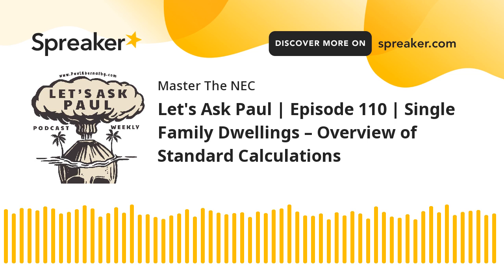Now you're saying, but didn't it say general illumination? Why are we adding the receptacles? Because 220.14(J) told us that all of this load is to be incorporated in one usable value. And that's what we're doing. So we're allowed to apply all of these, in case that ever gets confusing for you. Now, the second thing you're probably thinking is, well, yeah, but what about the small appliance and the laundry? Well, if you go look at 220.52(A) and (B), you'll notice in the very last sentence, it tells you that these can be subject to the demands of Table 220.42. So that's why we can lump them together and apply this table. Have you ever wondered how that works? Just go read the last sentence of 220.52(A) and (B).